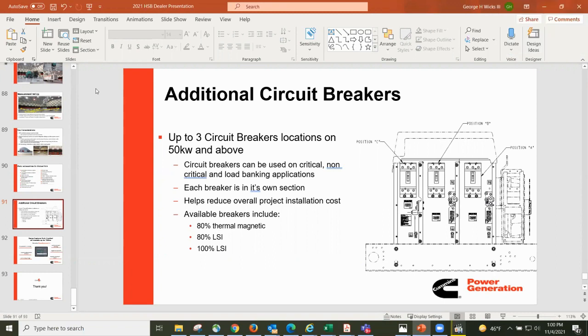Oh, so now they're using that same standard that we do in the code book, Article 240.4(B), that talks about up to 400 amps. You're allowed to rate up to the next highest size. Now it's not for generators, that section of the code book, but the concept is for everything. Yeah, 800 amps or less. That breaker size is what dictates our wire size, correct? Right. So you guys have to adhere to that. So yeah, with all the new controls and microprocessors controlling these generators, they're going to shut down before the breakers actually mechanically trip. If it's sensing maximum load, we're at the maximum fuel pressure now.